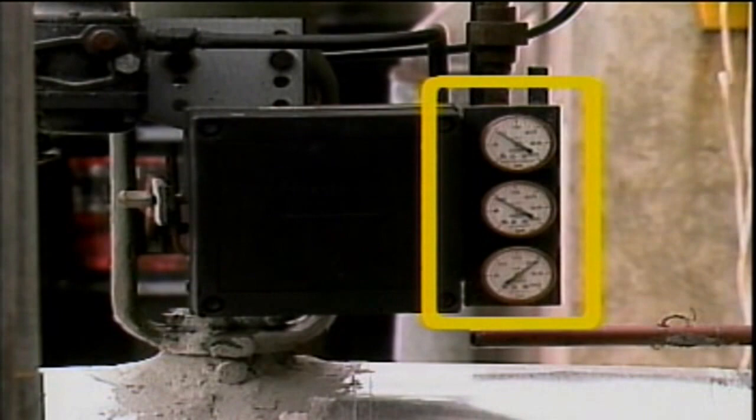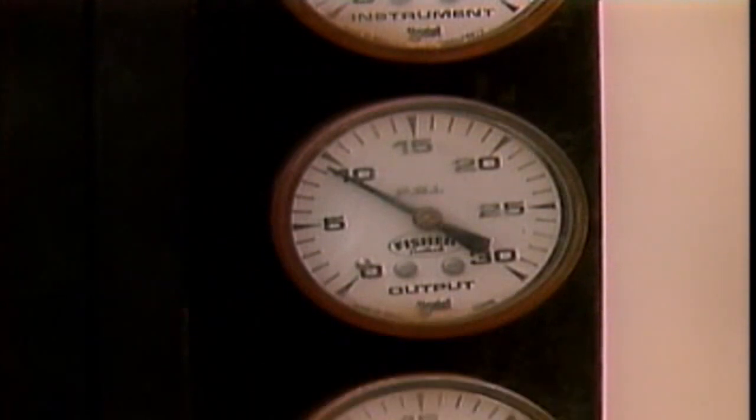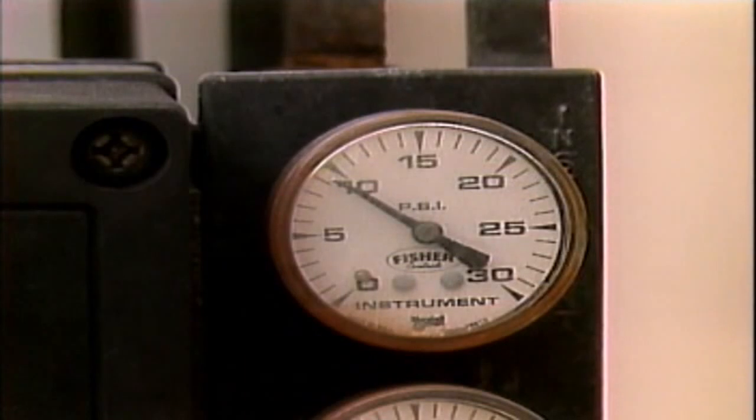The positioner shown here has three gauges. One gauge indicates the supply air pressure to the positioner, and another indicates the output air pressure to the actuator. The third gauge indicates the input signal pressure from the controller.